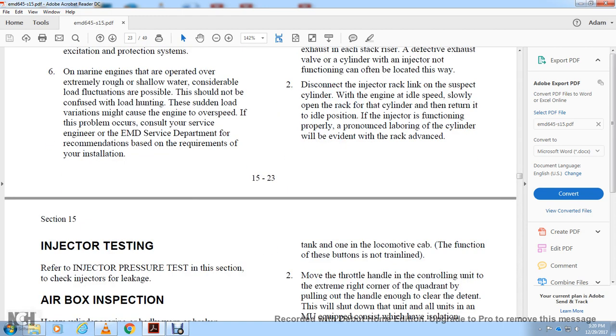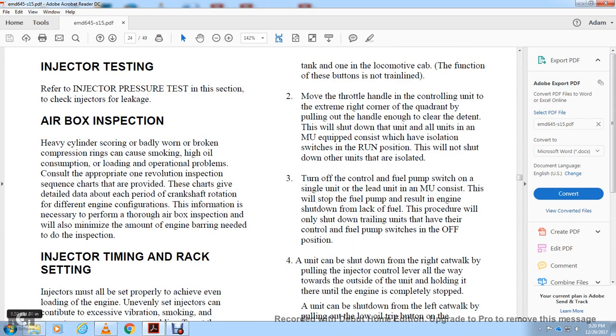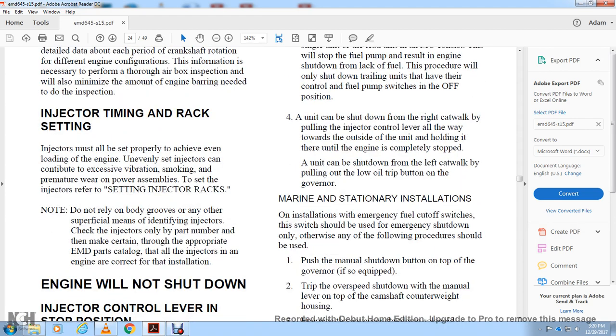If the injector is functioning properly, a pronounced laboring of the cylinder will be evident when the rack is advanced. Injector Testing: Refer to injector pressure testing in this section and check injectors for leaks. Airbox inspection: heavy cylinder scoring and badly worn or broken compression rings contribute to smoking, high oil consumption, and operational problems. Consult the appropriate one-revolution inspection sequence. The sequence provides detailed data about each crankshaft rotation period, engine configuration, and the information necessary to perform a thorough airbox inspection while minimizing the amount of engine barring needed.